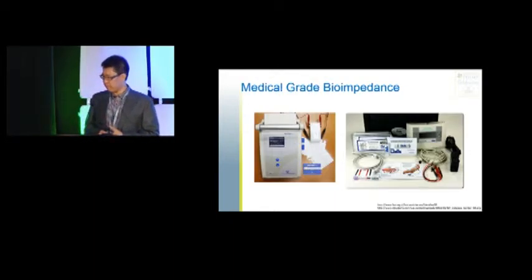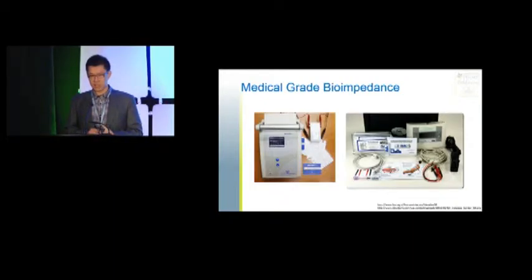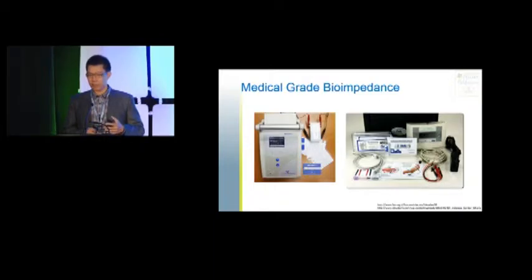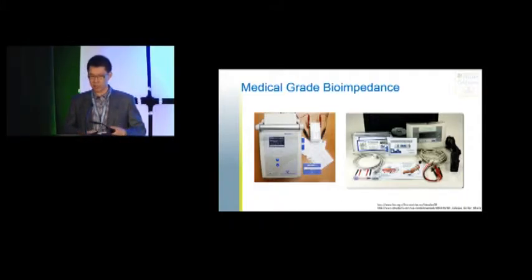These are the medical-grade devices. The one on the right is the RJL Systems, used in some dialysis and physiology studies. The one on the left is the Fresenius BCM monitor. They're both similar in terms of reporting, but the Fresenius machine actually has more frequencies and is compatible with the Fresenius 5008 dialysis machine cards. Both have been reported in the medical literature.